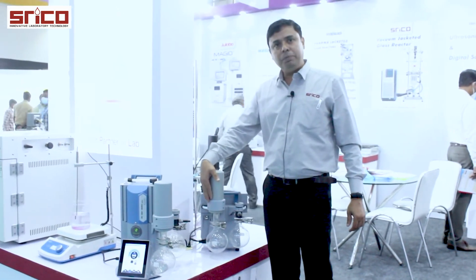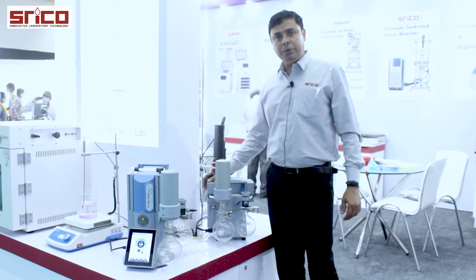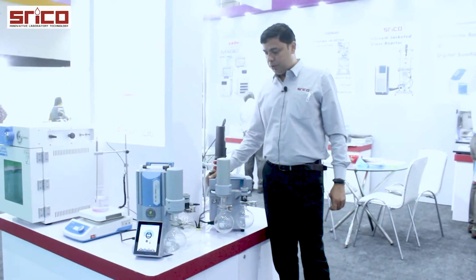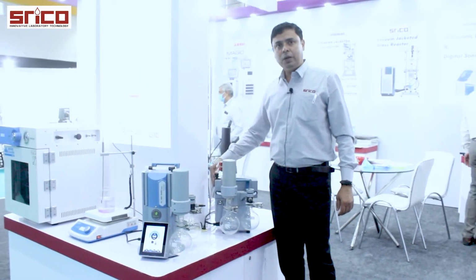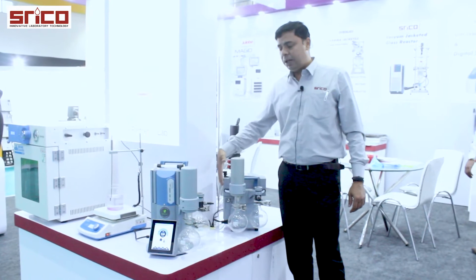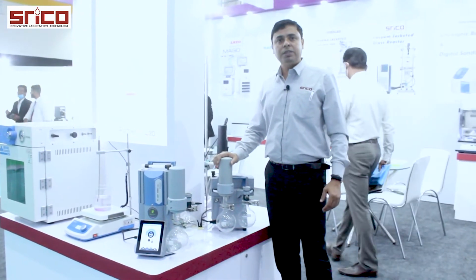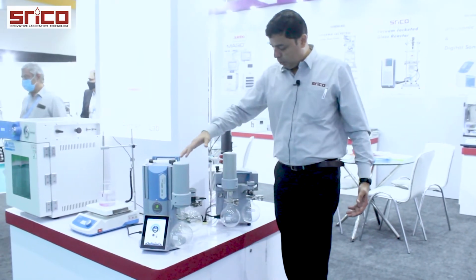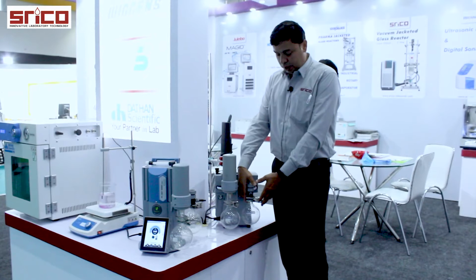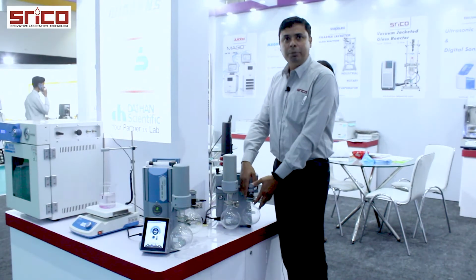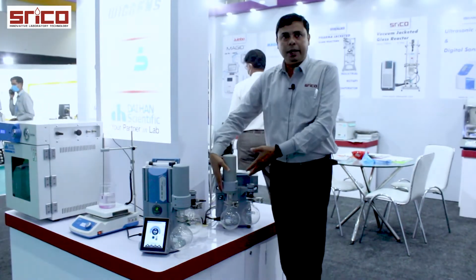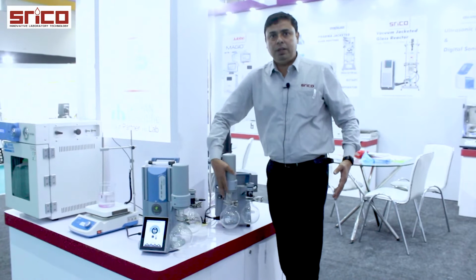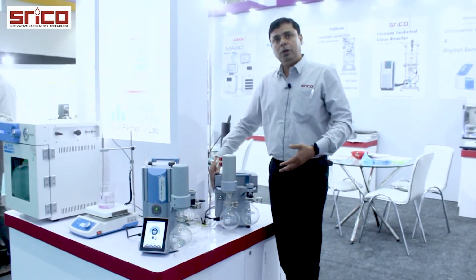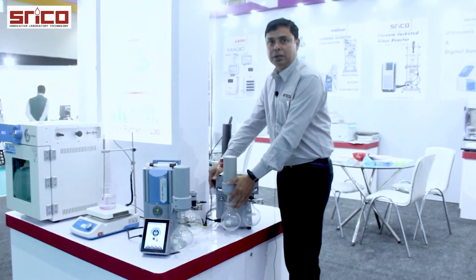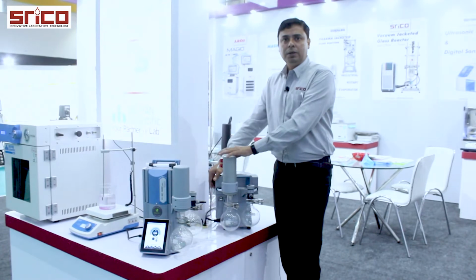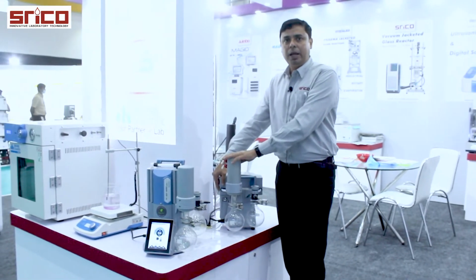These are oil-free diaphragm pumps from Vacuubrand, Germany. Really a world-class product with zero maintenance. There is no oil inside and all internal parts are coated with PTFE. These diaphragm pumps can give vacuum up to 0.6 millibar with vacuum controller. And here with the pump we are providing one catch pot on the suction side, so that if any powder material or any liquid is coming, it can be trapped inside before entering into the pump. At the exhaust side we have this condenser and a catch pot, so that if any vapor is passing through the pump to the atmosphere, we have one more chance to get it condensed and collect it. So we can save the chemicals exposure to the lab conditions.